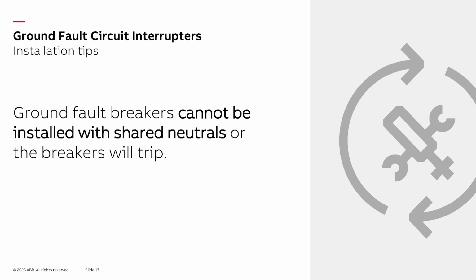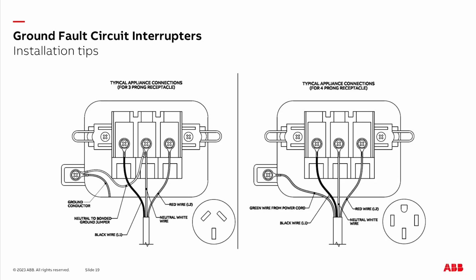Also, with a two-pole ground fault breaker being more prevalent in the 2020 code, please remember that for four-prong receptacles protected by ground fault circuit interrupters, if the ground and neutral are bonded in the appliance, the ground fault circuit interrupter will trip. The jumper bonding the ground and neutral needs to be removed if approved by the appliance manufacturer. Also, if you upgrade your appliance to a four-prong receptacle, you need to bring all four wires back to the breaker. If only 3 wires are brought back, it will trip the breaker.